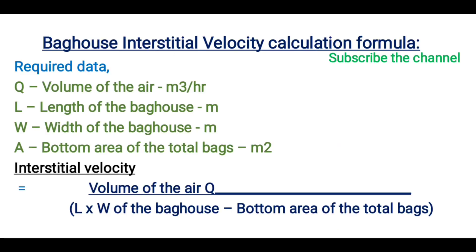How to calculate the interstitial velocity for the bag house. Required data: Q — volume of the air in cubic meters per hour; L — length of the bag house in meters; W — width of the bag house in meters; A — bottom area of the total bags in square meters. Interstitial velocity equals the volume of the air divided by the length and width of the bag house minus the bottom area of the total bags.